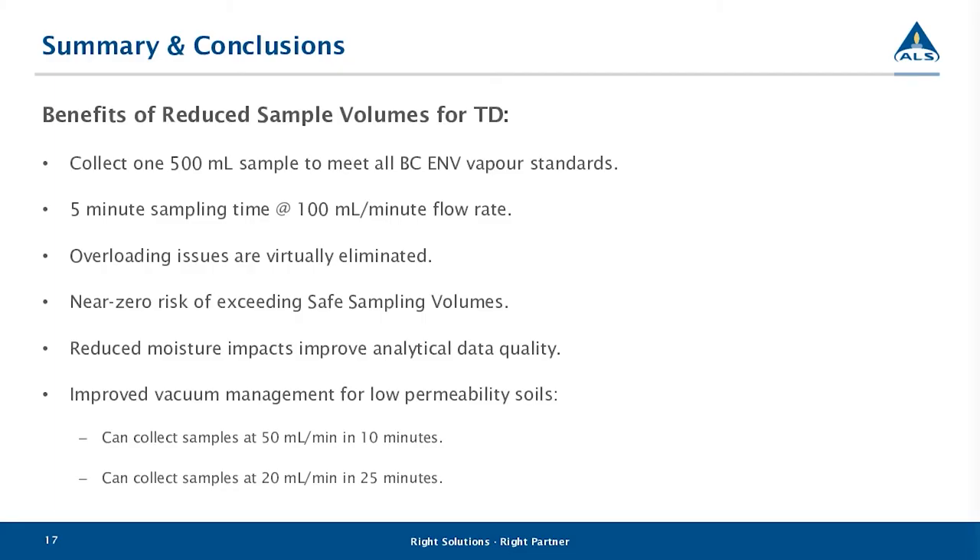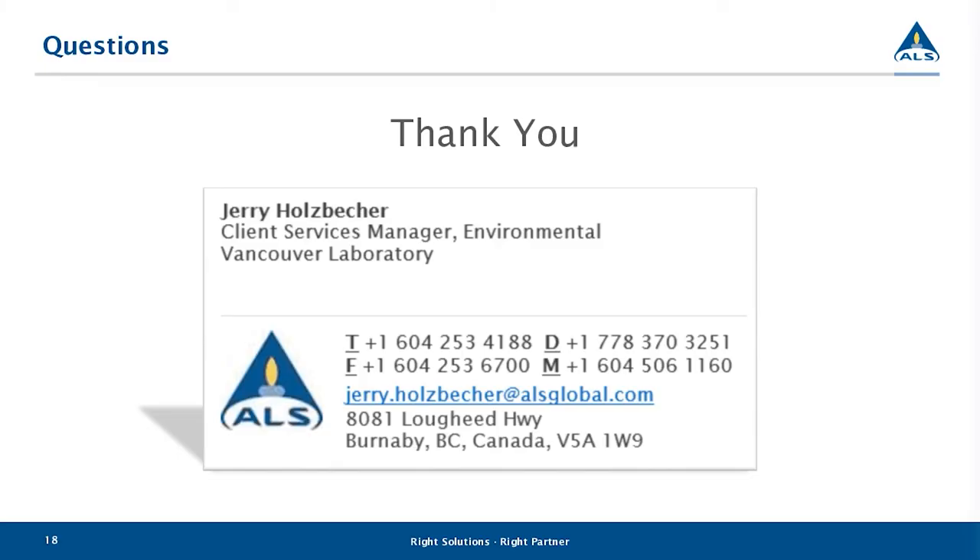In conclusion, in BC you can now collect one 500 mL sample to meet the BC ENV vapour standards. This is a five-minute sampling time at 100 mL per minute. Overloading issues with the tube and at the instrument are virtually eliminated, there is near-zero risk of exceeding safe sampling volumes, reduced moisture impacts, improved analytical data quality, and improved vacuum management at the well. Thanks for your attention, everybody — we'll now open the floor for questions.